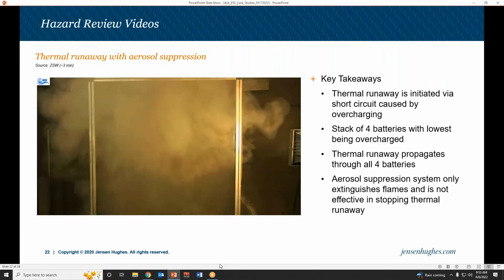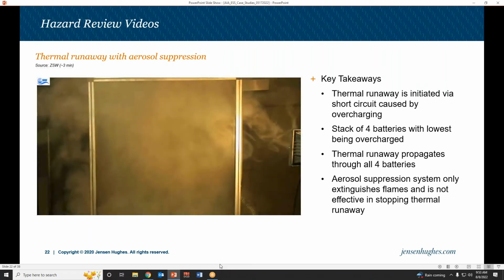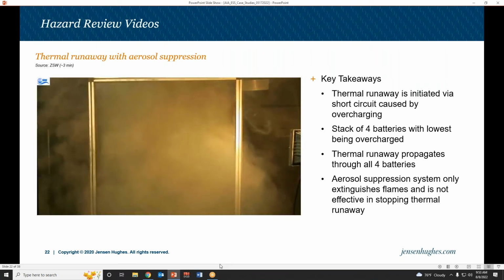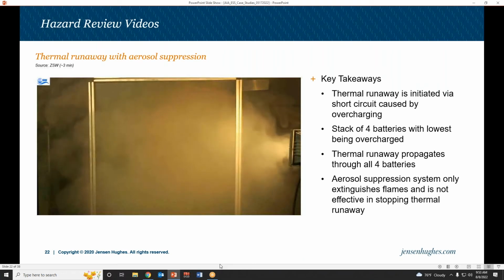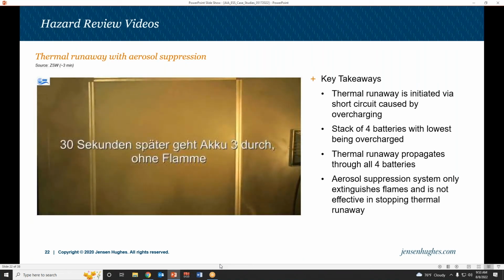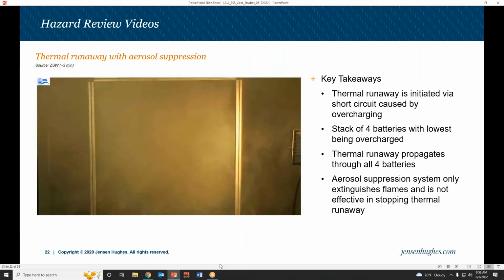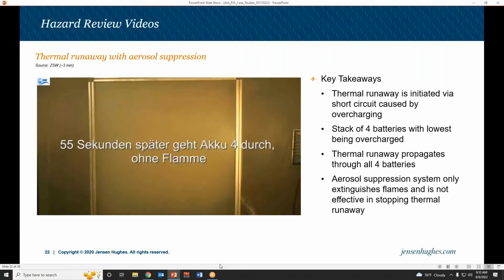And we've got two more to go. But the takeaway from this is the thermal runaway continues. So what the suppression system does is help kill the flames, but it doesn't stop the thermal runaway—you're not going to stop it, you can just control it and make sure it doesn't spread or propagate to adjacent racks.